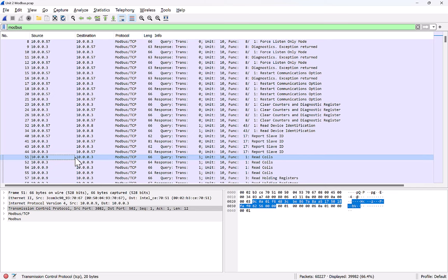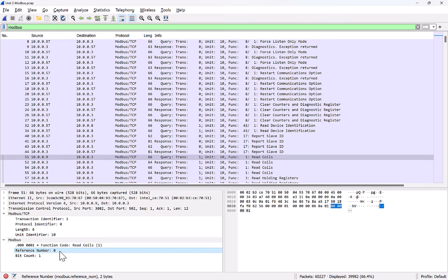And so if we expand down here under Modbus and Modbus TCP/IP, right, we can actually see that 10.0.0.9 is issuing a query for a coil. So it wants to say, give us a coil. I'm going to read the first coil, which is number 0. And I'm only going to get a single coil.